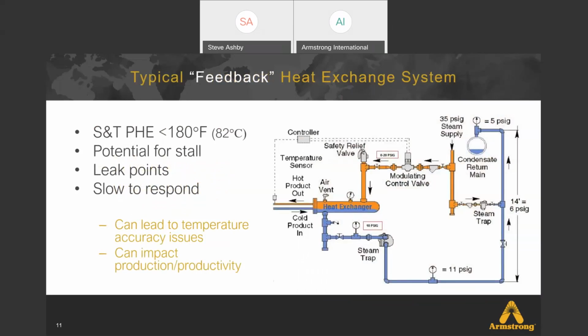So this is what we typically see when using steam boilers for generating hot water. This is just what we call a typical feedback heat exchange system. It can be a shell and tube heat exchanger or a plate heat exchanger. And this has some inherent design issues, potential for stall. Certainly, steam and condensate is an aggressive application, a lot of leak points, a lot of overall general maintenance, if you will. And then it's not necessarily fast to respond. As loads swing from high demand to low demand, it takes a while for all of those parts and pieces to get temperatures at a set point, and that lag time can certainly impact everything that it's serving in the plant.